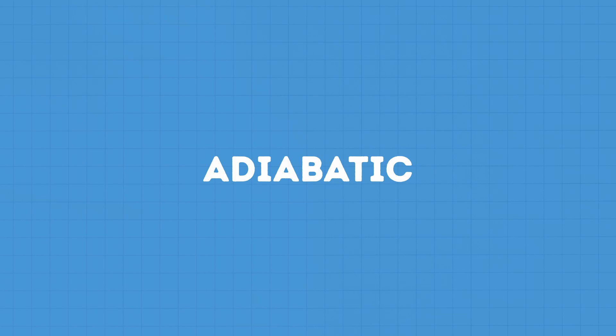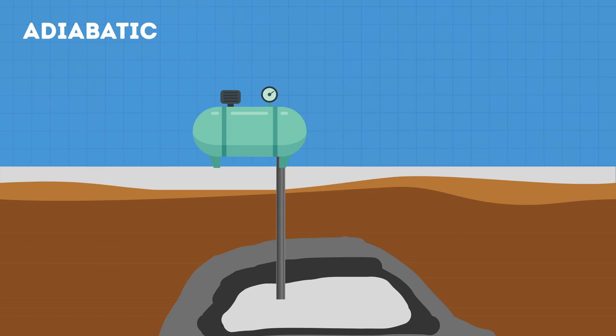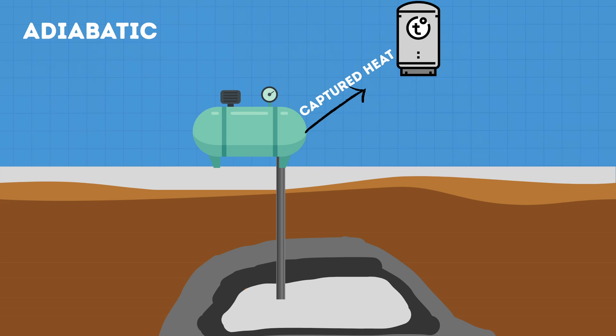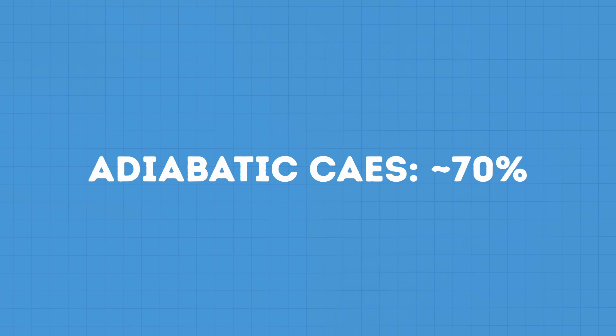Adiabatic is an improvement to the diabatic system. Since gases heat up when compressed and cool down when expanded, adiabatic systems capture the heat at the compression stage and store it in a thermal energy store — which can contain gravel — which is then reused to heat up the air when expanded. Due to utilizing the heat within the system and not needing to add natural gas, adiabatic CAES can achieve 70% round-trip efficiency, whilst diabatic achieves around 45%.